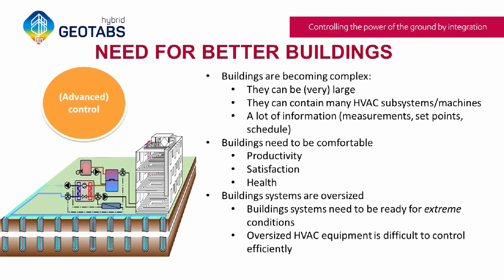Comfort is firstly achieved by having a good design of the building, and secondly by having good control. Finally, something which is always a problem is that the HVAC of buildings is oversized for daily use. Even if you don't add any safety factor to your design, you still need a building able to provide enough heat on the coldest day outside. But most of the time it's not the coldest day, so you end up with a system that is oversized and then difficult to control well.